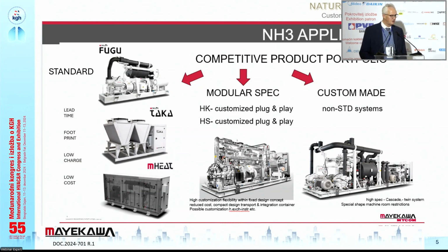and can deliver up to 260 kilowatt cooling, same temperature, the water cooling 12 to 7 or even lower, down to -10 is possible. Here again the same story. Lead time is minimized. Of course, those units have a very compact footprint. They are easily transportable by normal trucks. And there is a very low charge of ammonia in these systems. The TAKA, for example, mostly below 30 kilo per unit. And for the top one, it can go up to 60 kilo.